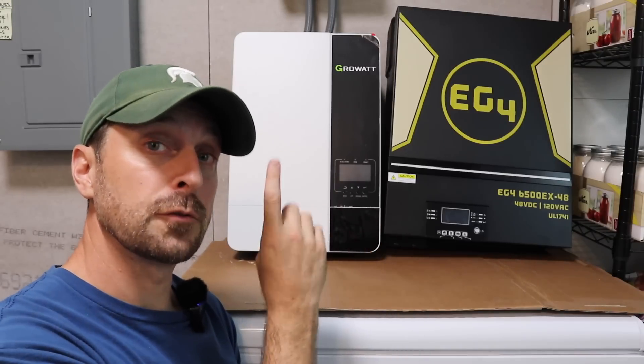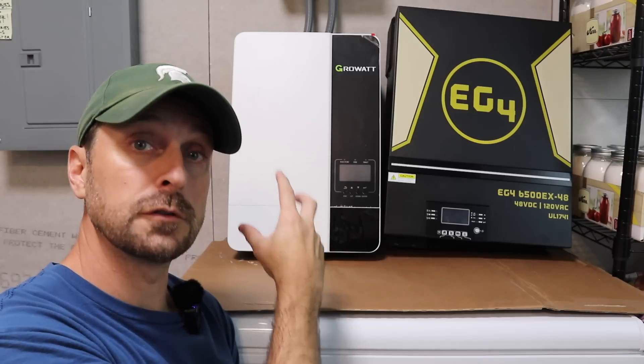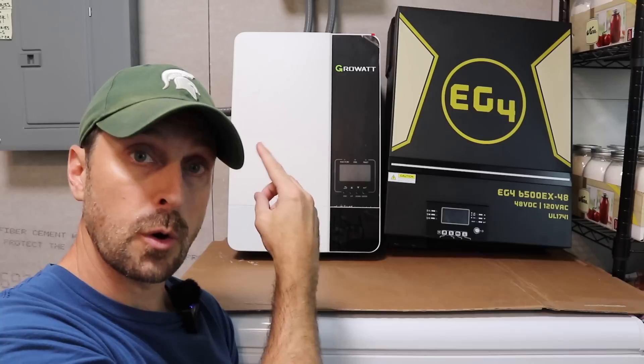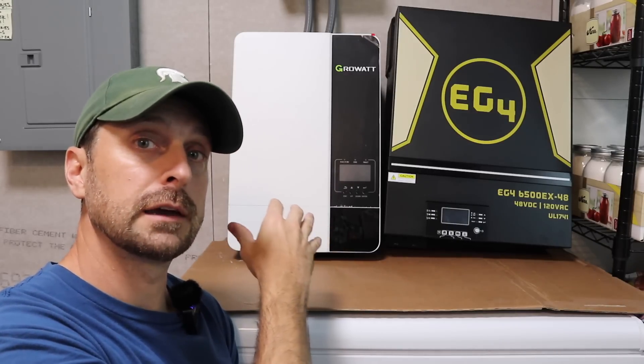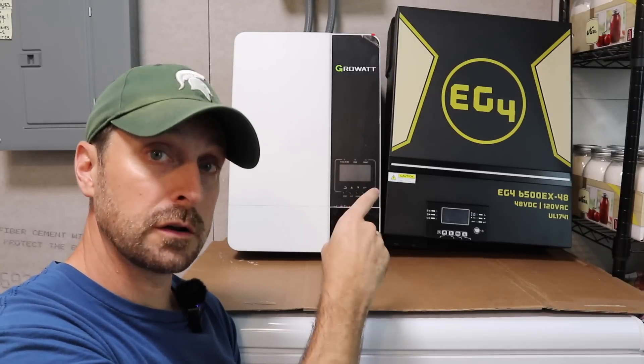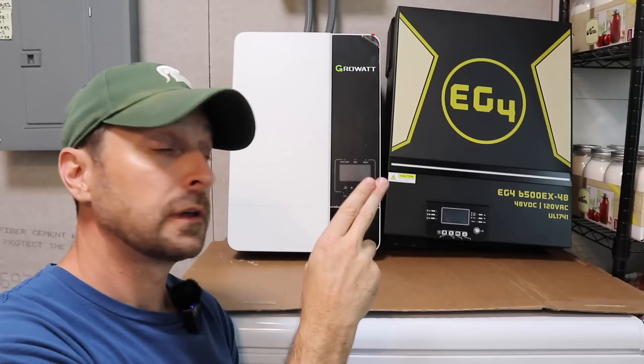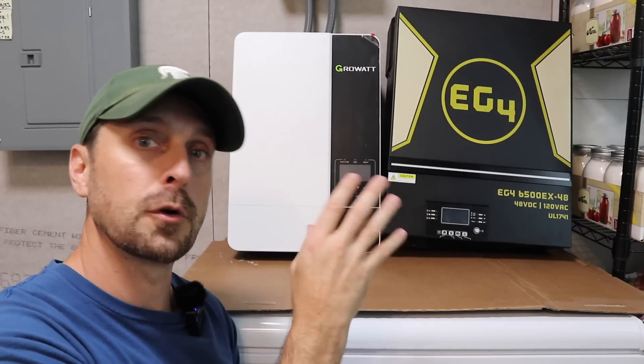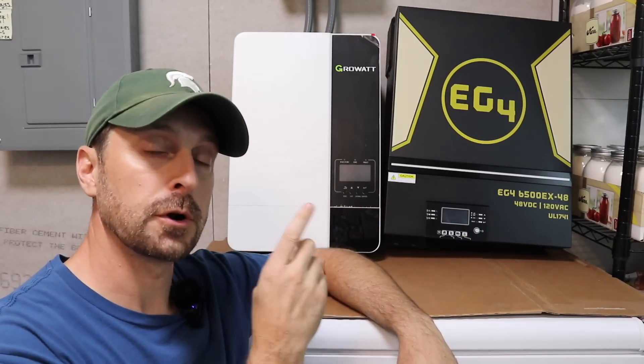Here's one of the key differences. The Growatt is a 240 volt inverter, so to get it to produce 120 volts for your home you needed a transformer — like the Growatt transformer or the SolarEdge midpoint transformer — to split it into a neutral leg so you had both 120 and 240 for the house. The EG4 is a 120 volt inverter, so you have to have two of them to create a split-phase 240 volt output for your big loads like your dryer, stove, and water heater.